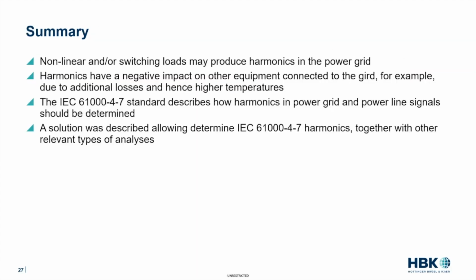So, coming to the last part of my presentation, the summary. What we have seen is an increase in nonlinear and/or switching loads, and they produce harmonics in the power grid. Harmonics have a negative impact on other equipment connected to the grid, for example due to additional losses, higher temperatures, etc. The IEC 61000-4-7 standard describes how harmonics in power grid and power line signals should be determined. And I discussed a solution on how that can easily be done. So that is basically it.